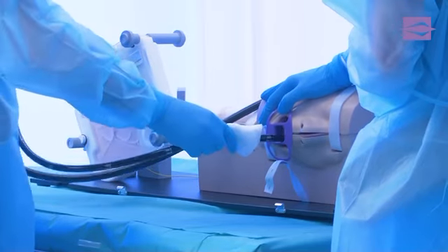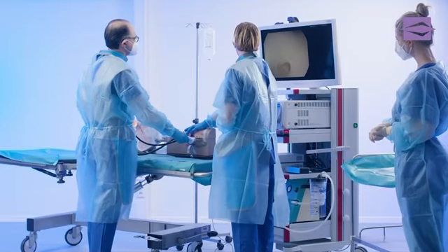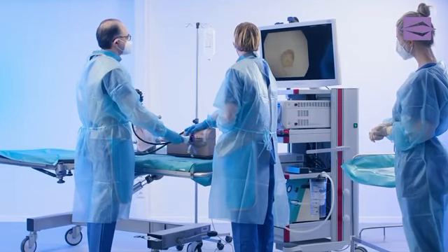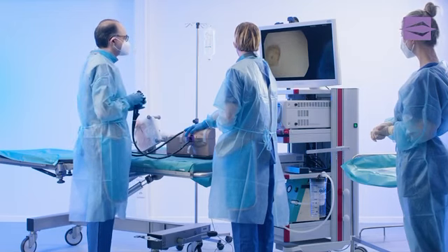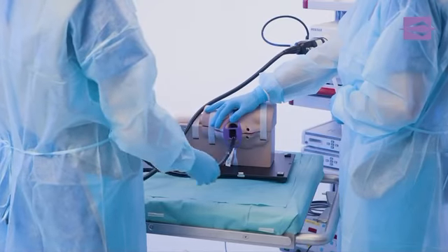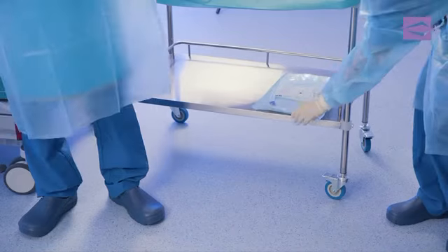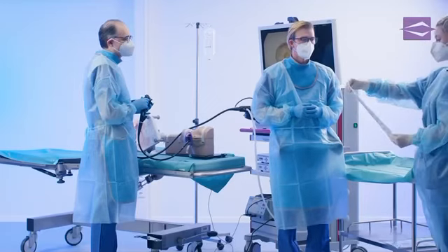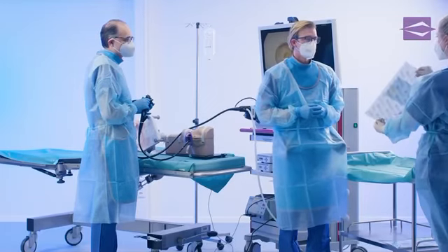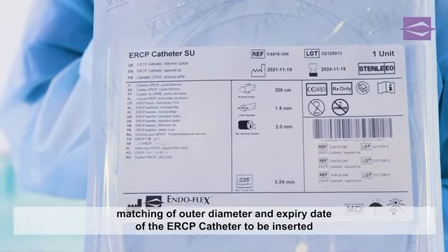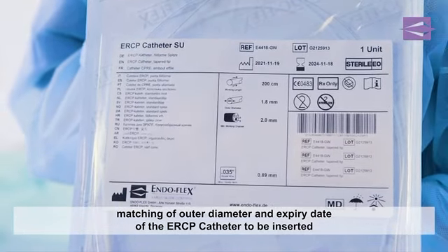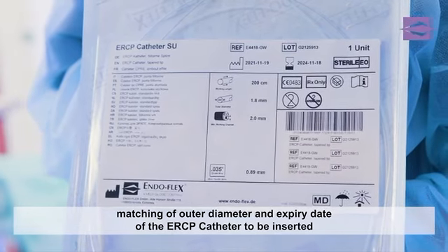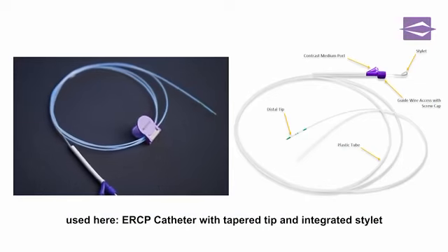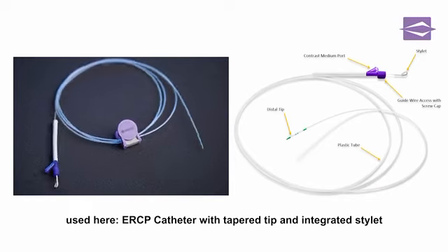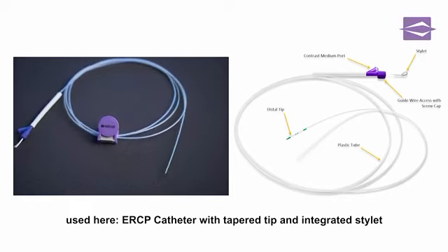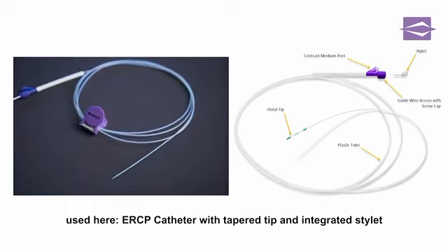The examiner advances the distal end of the duodenoscope until the target, the papilla, can be clearly identified through the lateral optics. After positioning of the duodenoscope, the previously selected ERCP catheter is handed over. The assistant compares the outer diameter of the catheter and the sterility expiration date with the label on the pouch. In this demonstration, we use an ERCP catheter with a tapered tip and integrated stylet for stabilization.